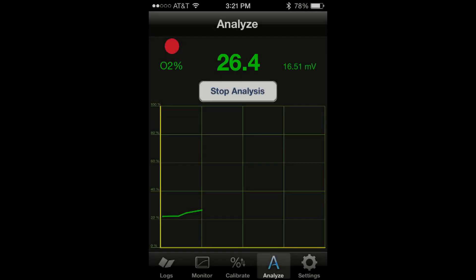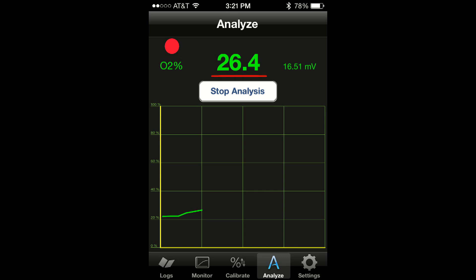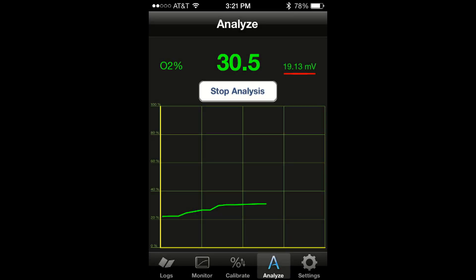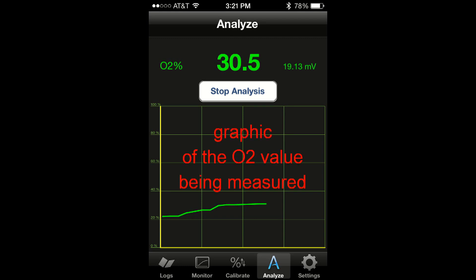During an analysis, the analyze screen contains the following indicators: analysis in progress indicator, the percentage of oxygen, and also the output voltage of the sensor. Additionally, it contains a graphic of the O2 value being measured.